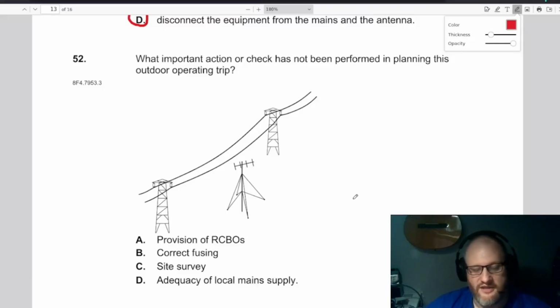For example, if within an earthed chassis a mains live wire were to accidentally short the chassis, that would cause current to flow from live through to earth, and the RCBO would detect that and cut off the main supply. There's also the O, which stands for overload, detecting a high current condition, almost like a resettable fuse. So if there was some kind of short not detected by the residual current breaker, it would detect a high amount of current flowing and cut off the main supply. Probably not going to help us in this situation.